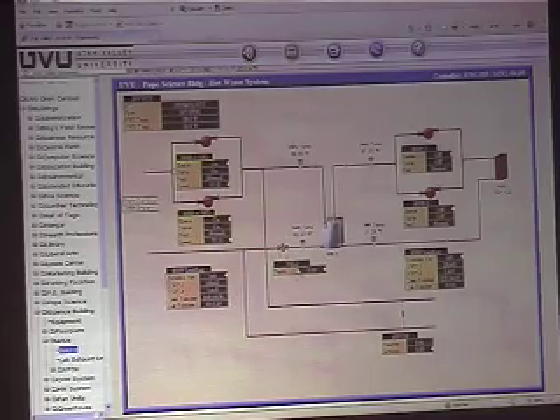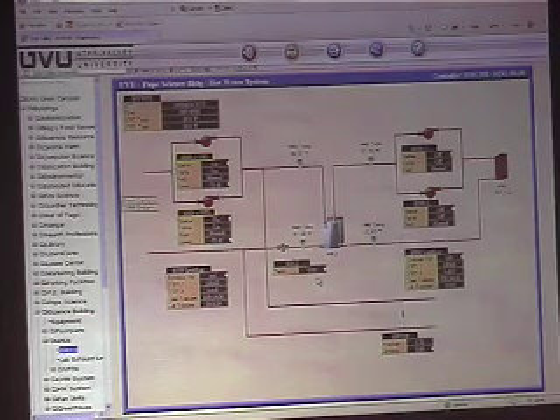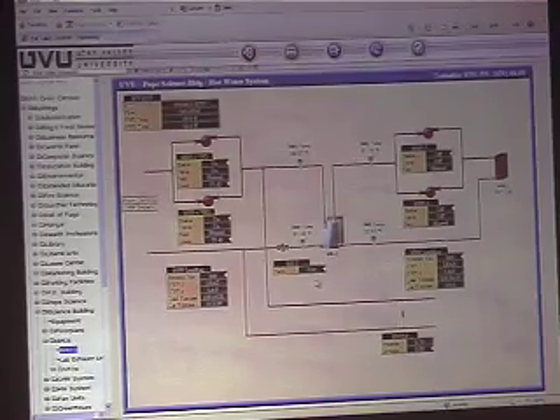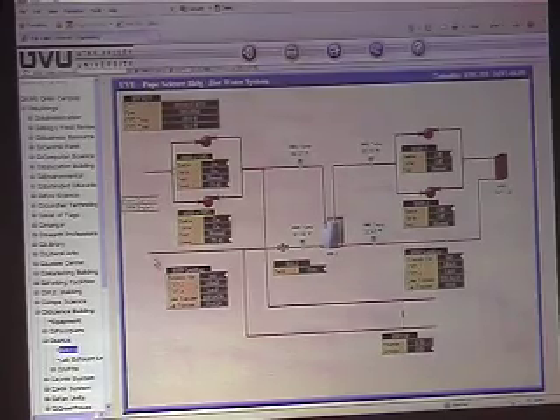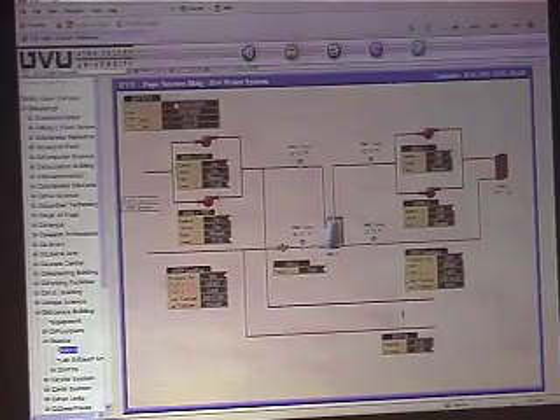This heat exchanger valve here controls your water temperature out to your coil here. So this is controlled off of the discharge air temperature PID loop. There's a BTU meter up there that we've got monitoring your supply and return temperatures right there, as well as the flow that generates your BTU. This is total BTU consumption of the building.